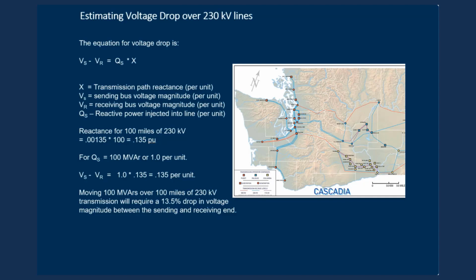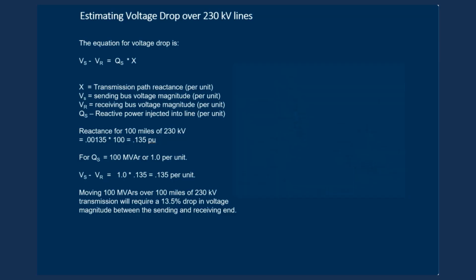We suggest that you work with your transmission operating engineers and decide, before you apply this to your system, whether to look at the typical reactance per mile of your actual circuits to see if you can use the same value or should use a modified value. The principles we cover here are applied to a combined 500 kV and 230 kV system, but the exact same principles can also be applied to systems with other voltage levels, for example, 345 kV, 765 kV, and 138 kV.